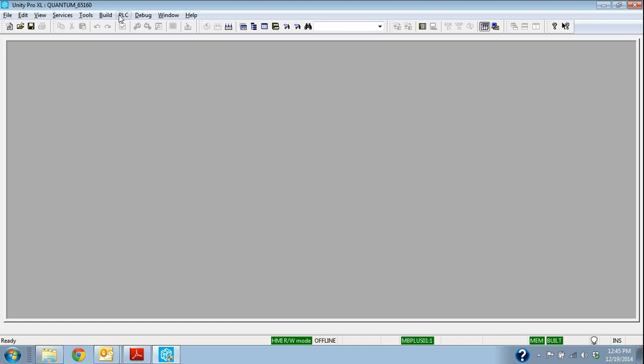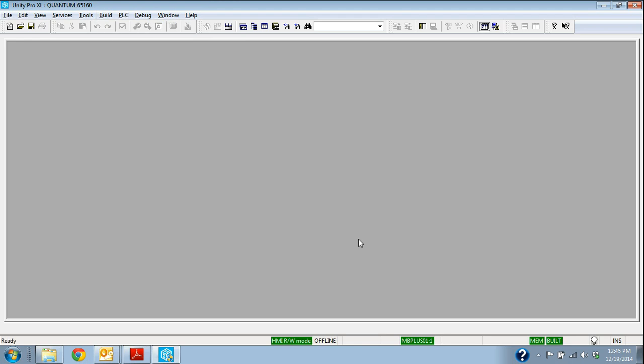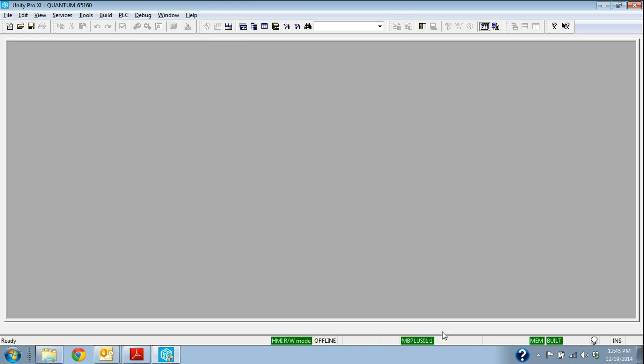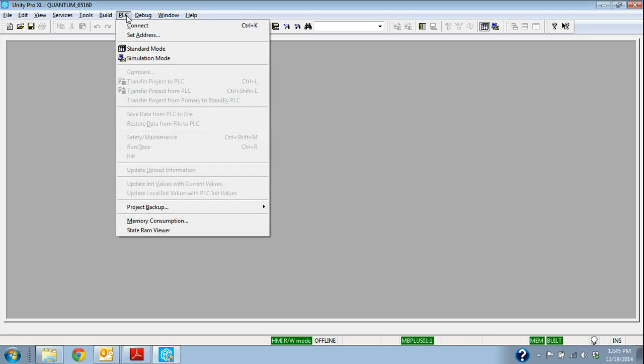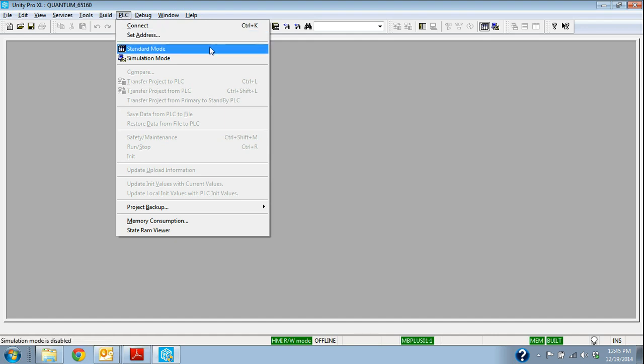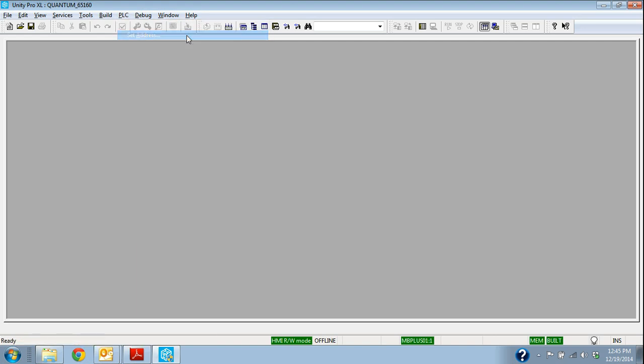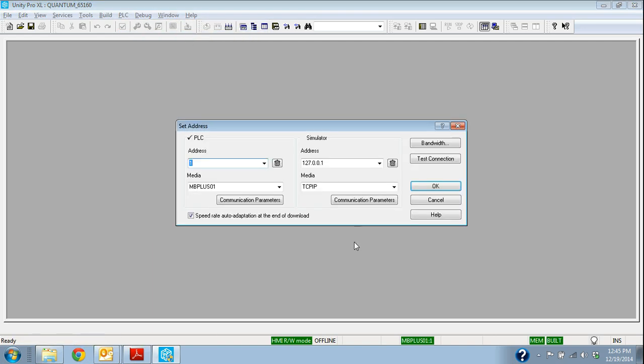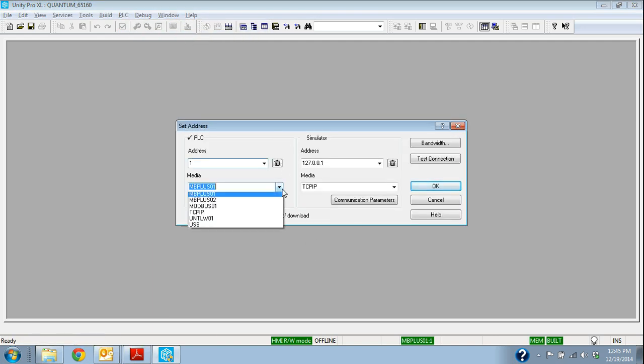We need to go find the controller. So in this case, we're hooked up via USB. We can see on the bottom here that we are offline right now, but we're set up to go Modbus Plus. Well, we're actually hooked up through a USB port, so I need to go under PLC. I am in Standard Mode, but I need to go to Set Address because we're going to use the USB port.